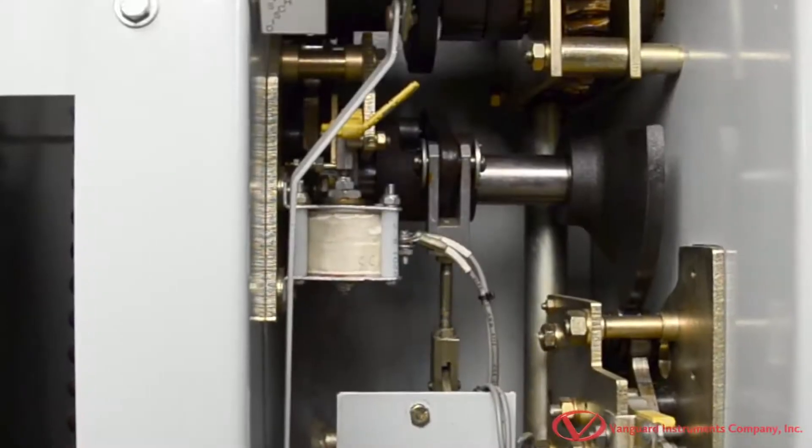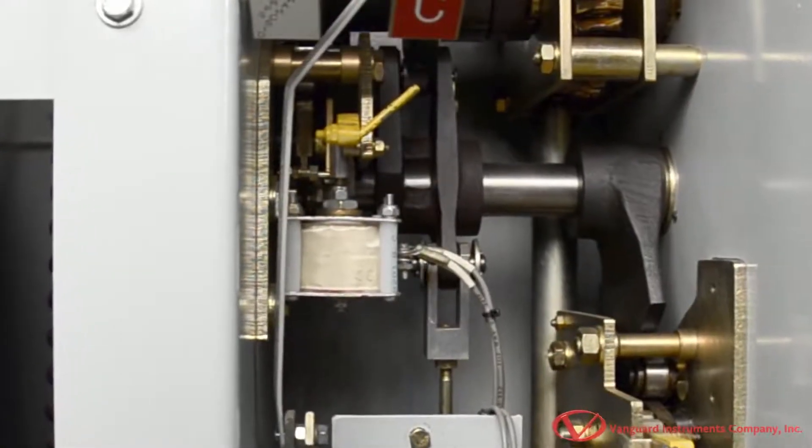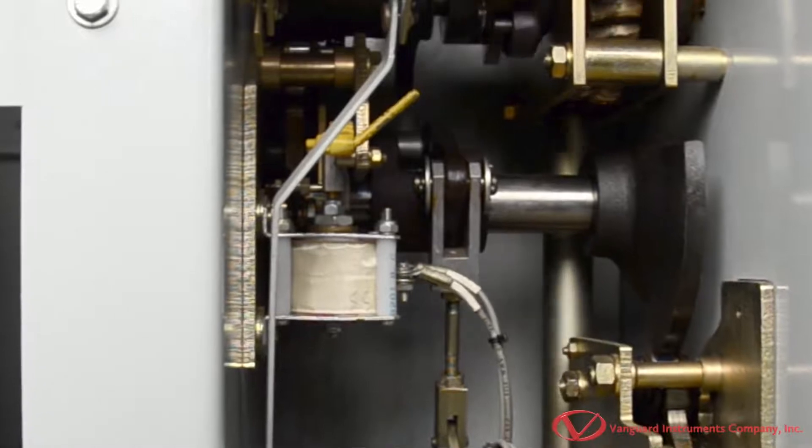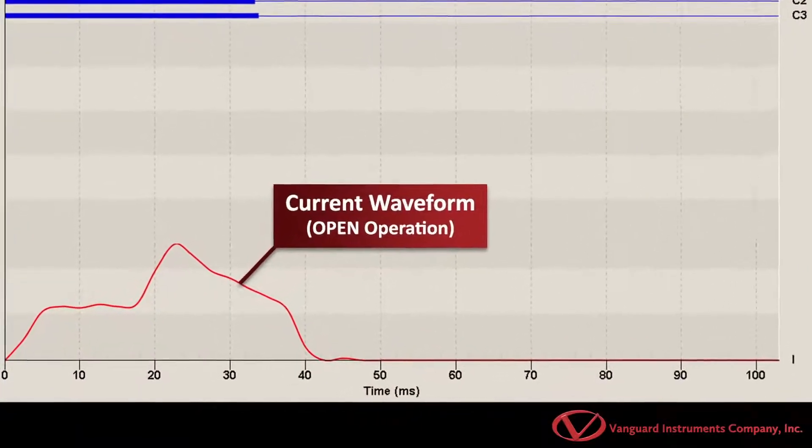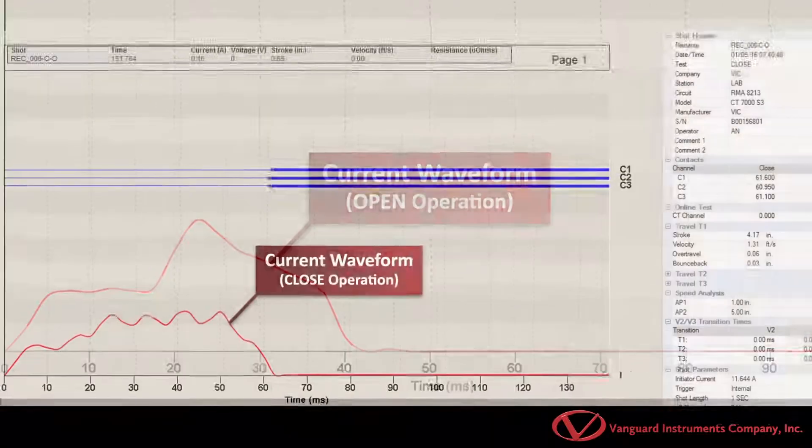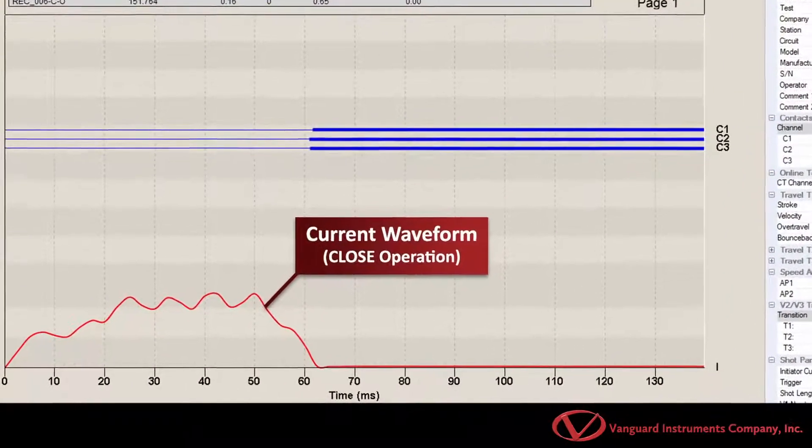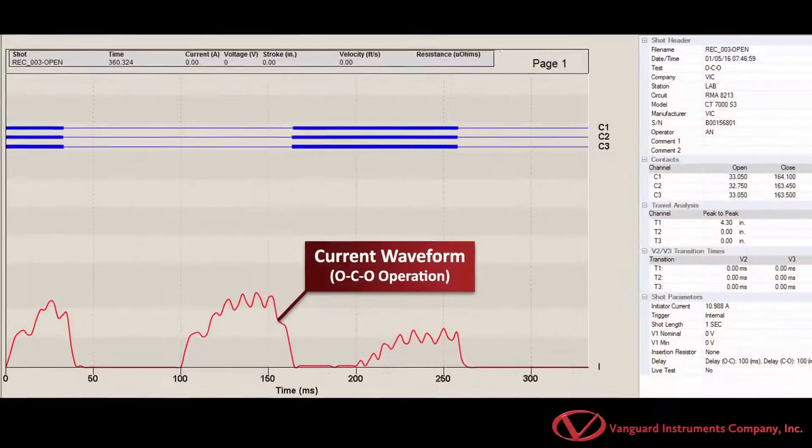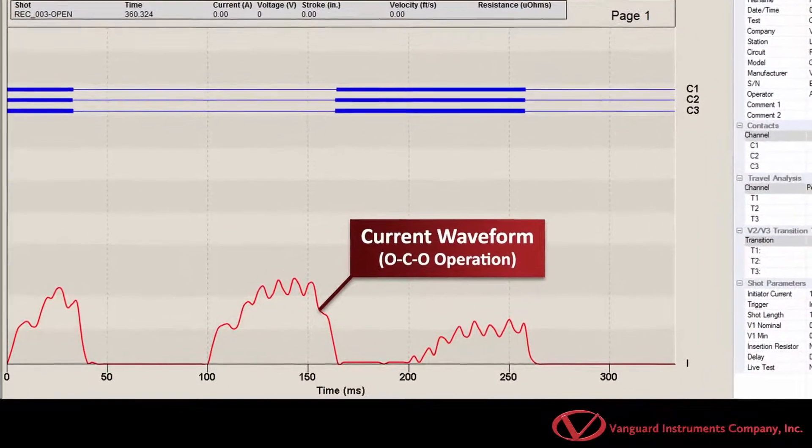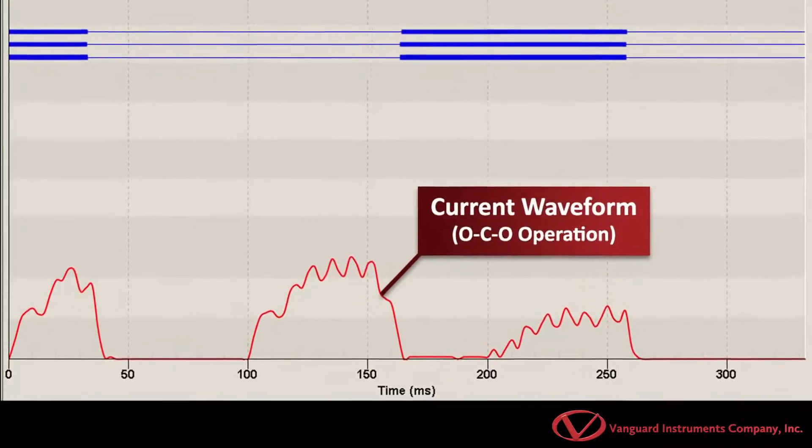A breaker's control circuit can also be tested by measuring the trip and close-coil current and the minimum pickup voltage. The measured values are then compared with the manufacturer's specifications to ensure optimal performance. The operating coil's current waveform provides insight into the mechanical and electrical condition of the operating coils. Any significant changes from the benchmark test signature should be further investigated.